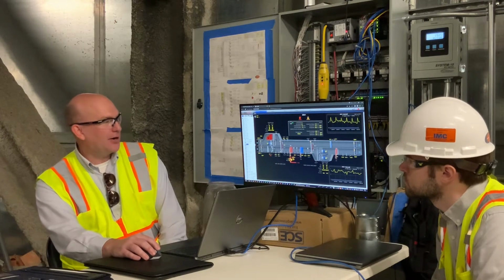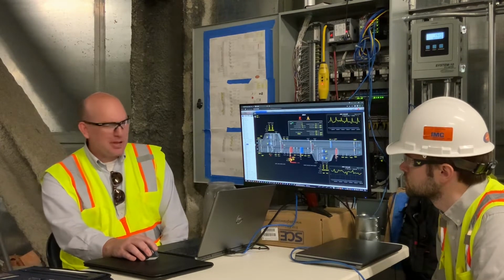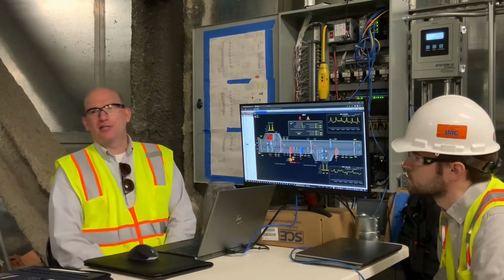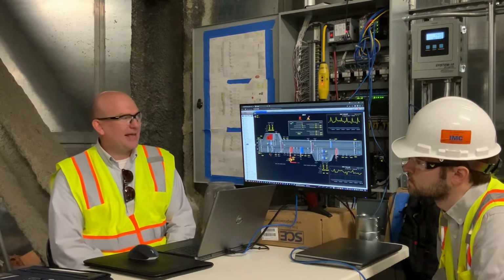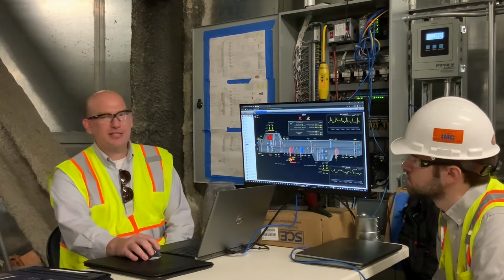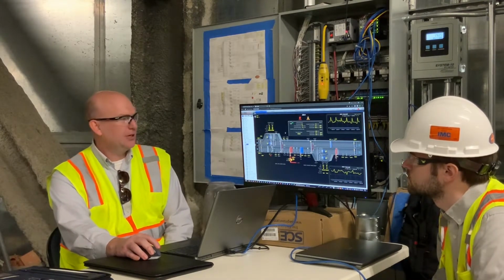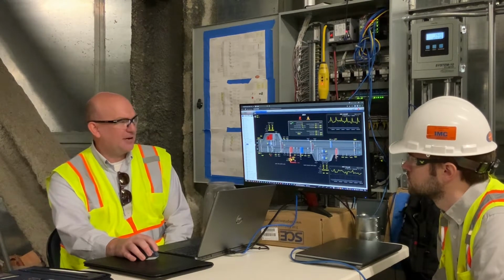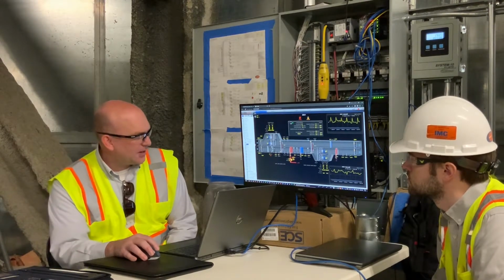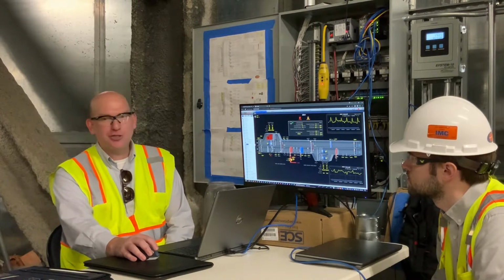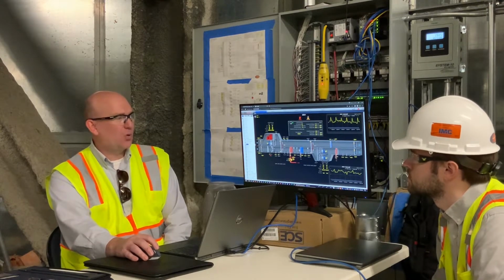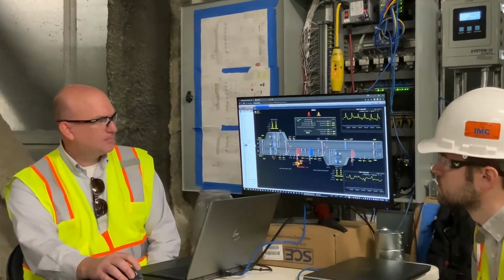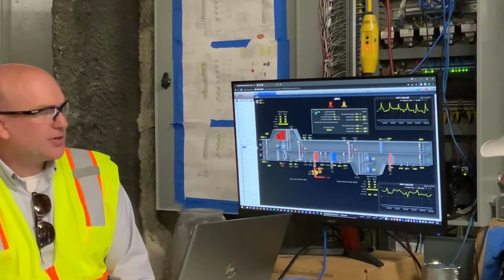Every point that you can monitor we have, and maybe that's a good opportunity to start to talk about safety, right? So we have pressure monitoring on the supply and the exhaust to protect the ductwork from the fan pressure. We also have a freezestat array associated with the entering air of the chilled water coil that is designed to protect both the chilled water coil and the hot water coil. What other safety am I missing?